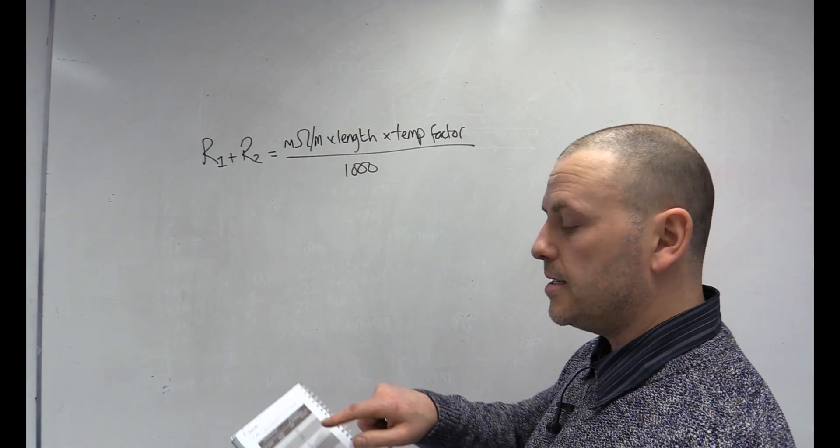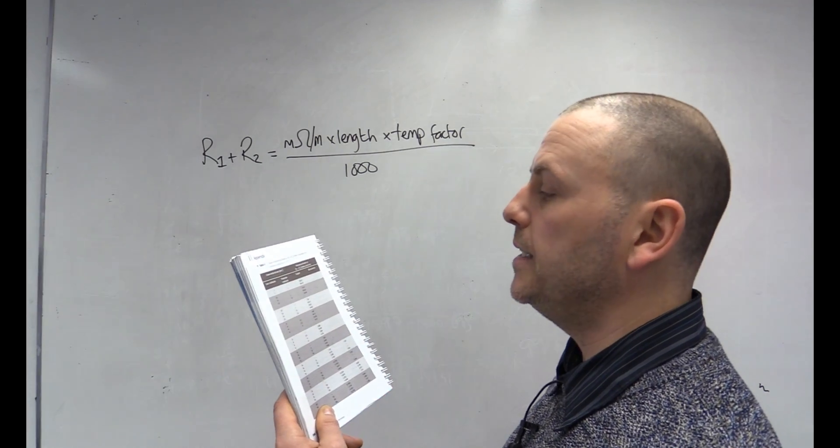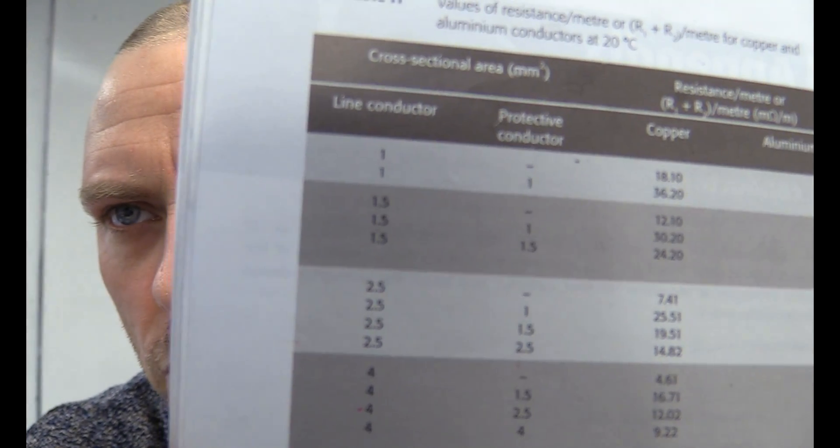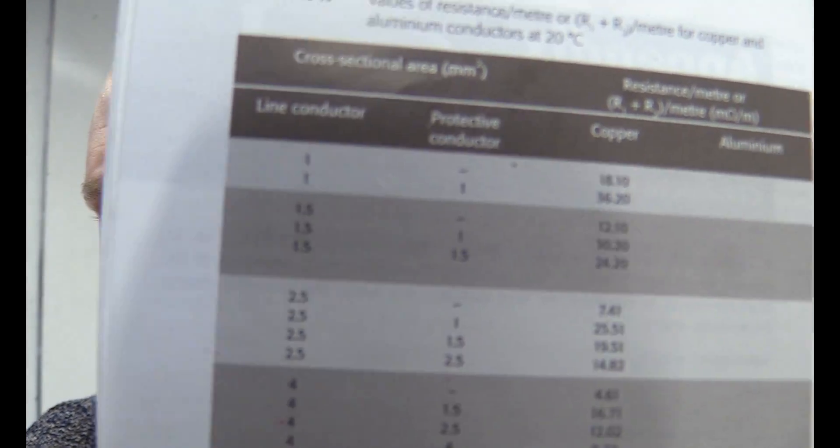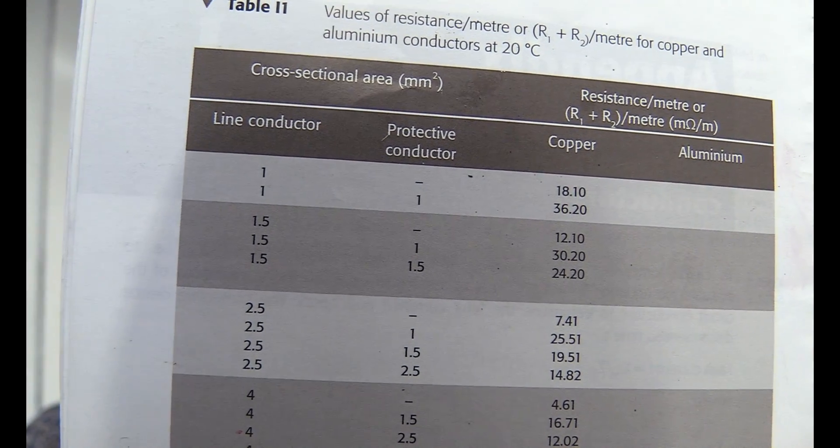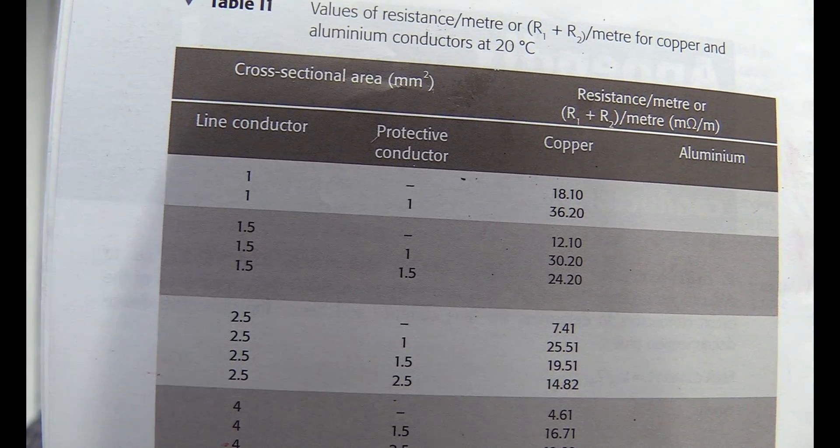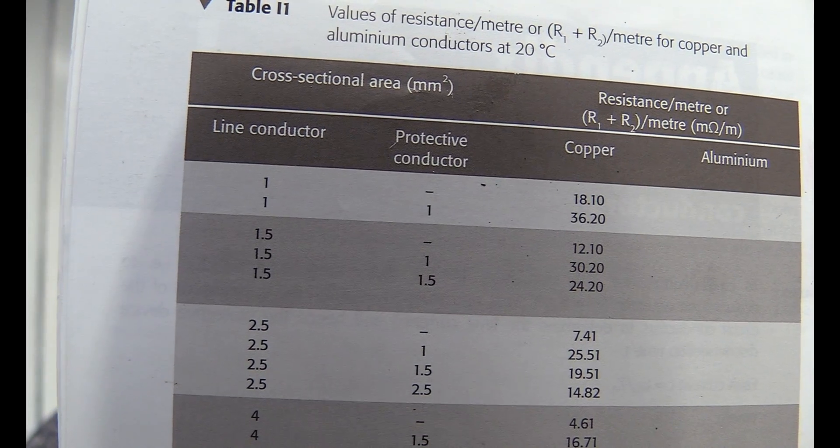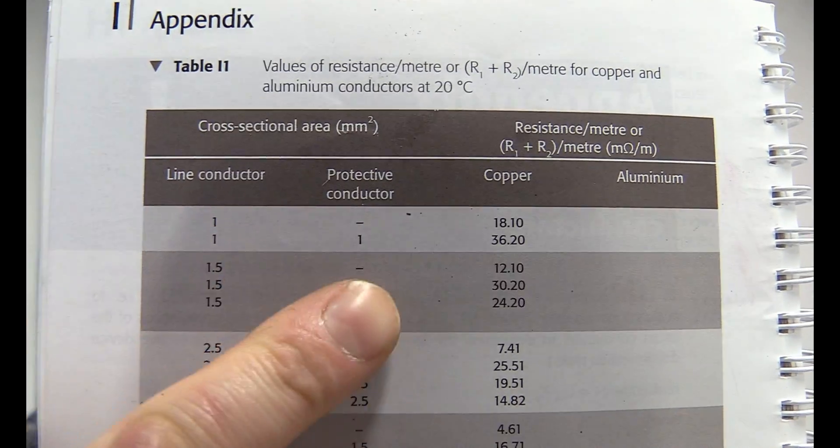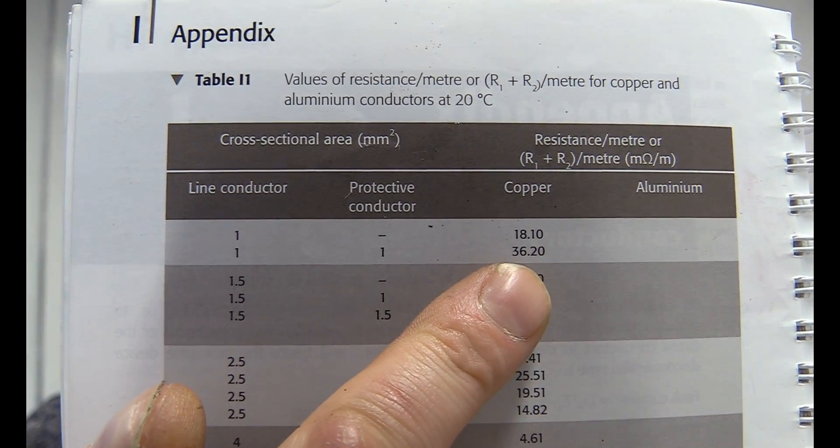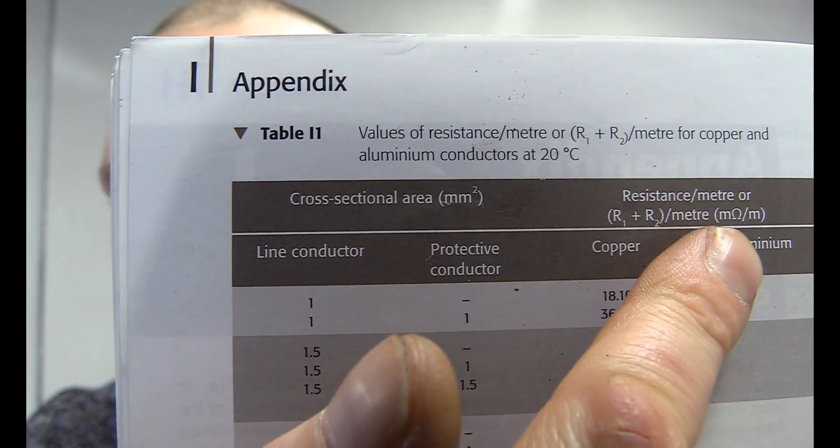Now, this table gives us a milliohm per meter value for different types of cables. You can see for a 1mm line conductor and a 1mm protective conductor, we get a value of 36.2 milliohms per meter.